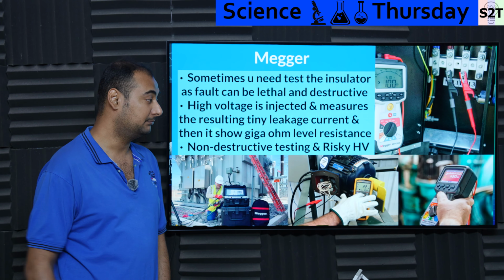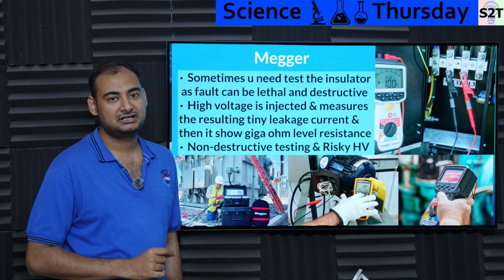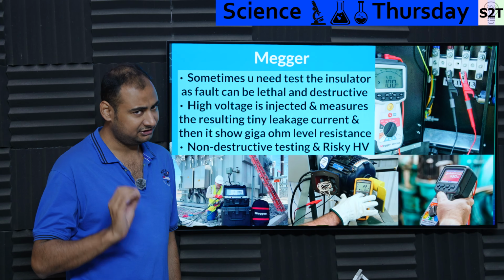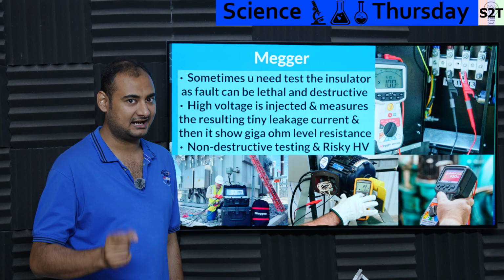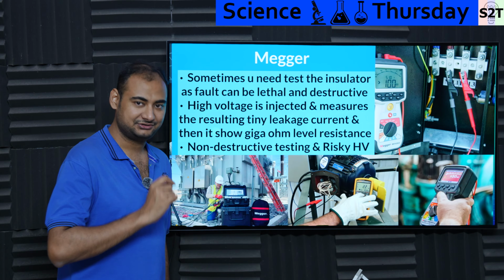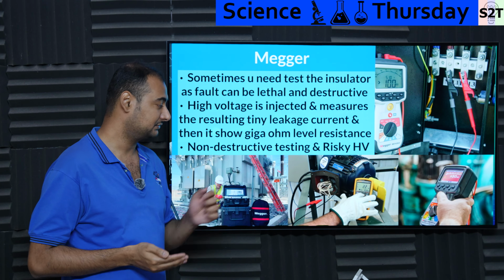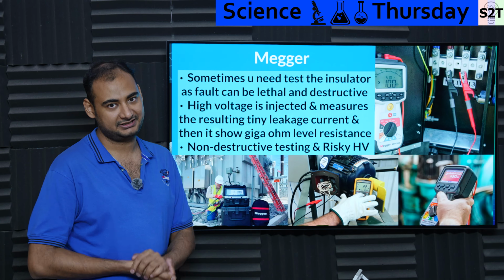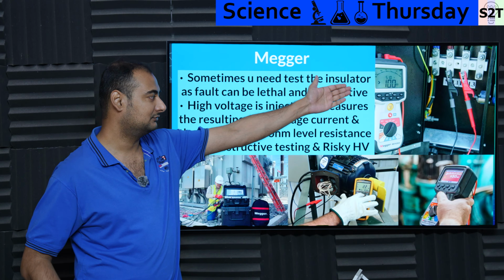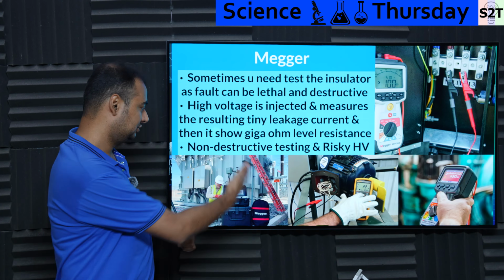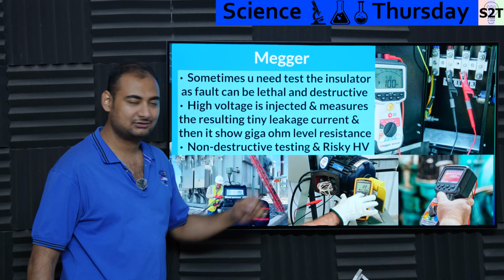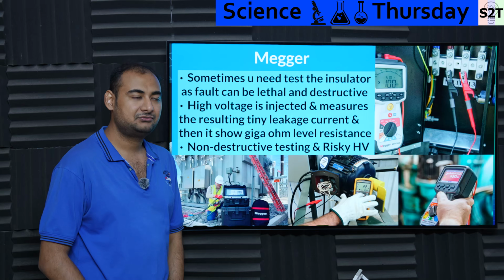It works great, but it's injecting a high, very short pulse. That's the good part. The bad part is it's still high pulse energy that you're trying to push through the insulation, so if you use too much of it, it will degrade it. For example, if you use this sort of meter designed for a substation grade system and force it on an AC mains motor, it will degrade it.